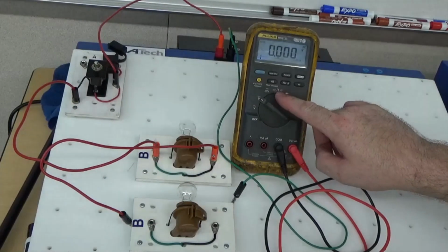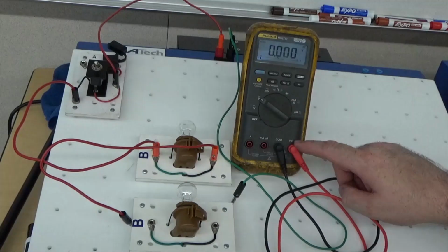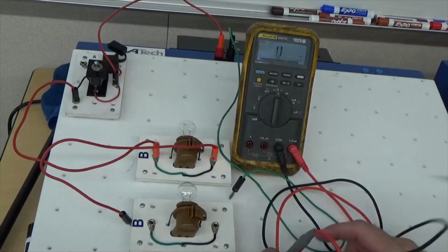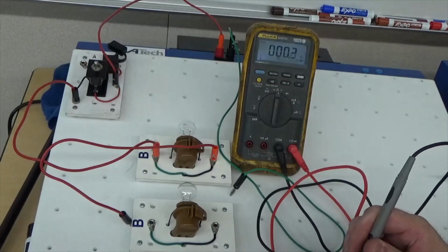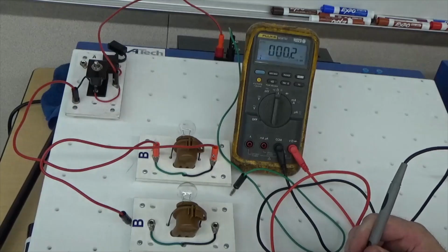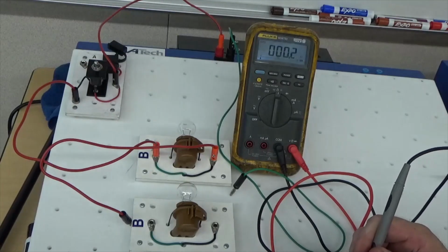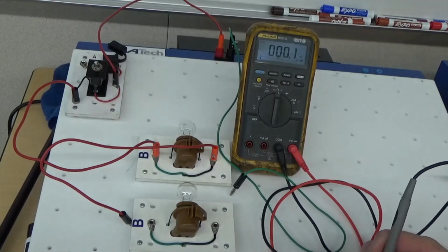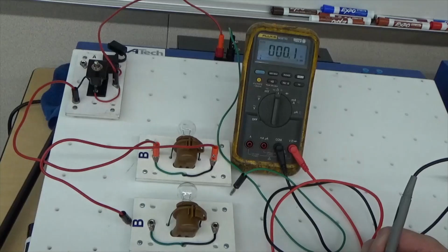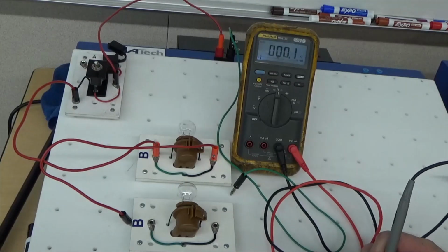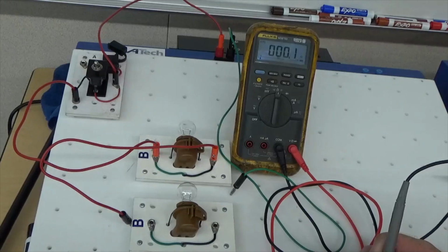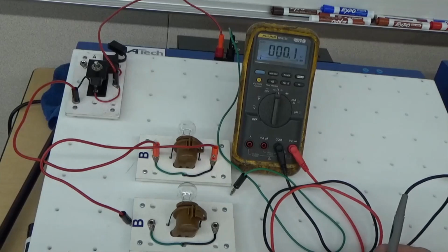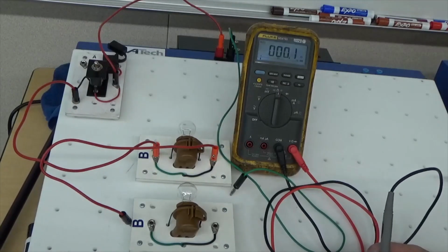So you're going to go ahead and go to resistance up here. Keep this in the same hole because it's got the ohms right there. Poof. Okay. Touch your leads together. Okay, these leads have 1/10 of an ohm, 2/10 of an ohm for resistance, so we're good. A good conductor is only going to drop about 1/10 of a volt max or have 1/10 of an ohm resistance. Very low resistance, very low voltage consumption, okay? And any good conducting path, that is the wire, that is a switch, that is connections and things like that. The only place you want consuming voltage is your loads.